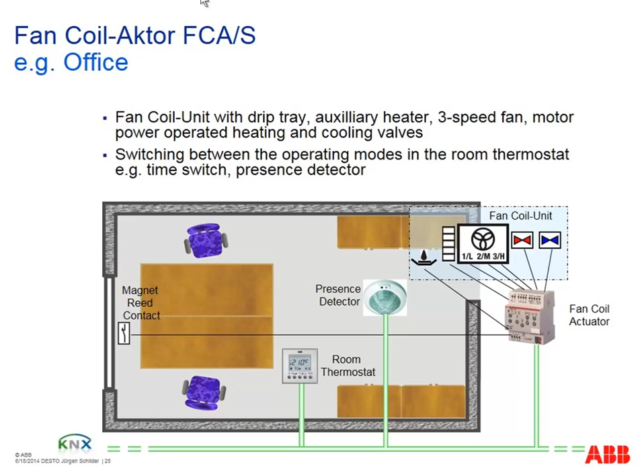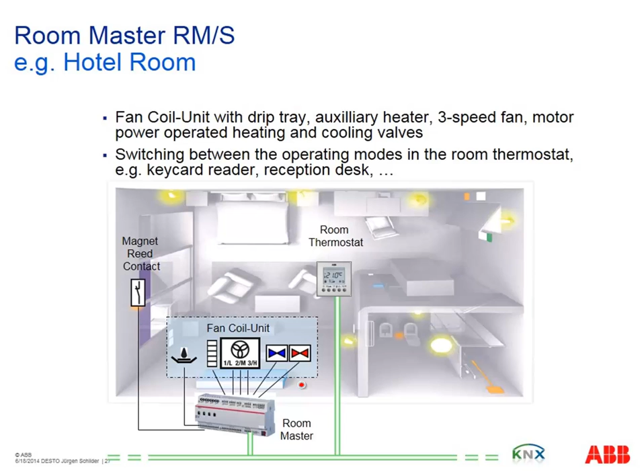Example for an office room, the same we can do of course in a hotel room. A very typical situation, fan coil units, very often used in hotels, and the same situation based on the fan coil actuator. And some of you might know the same can be done with a room master. The room master is a multi-I/O device. The room master 1.1 and 2.1 has these fan coil outputs integrated to do the same as seen before with a fan coil actuator. Not only for hotel rooms, but very often used in such projects.